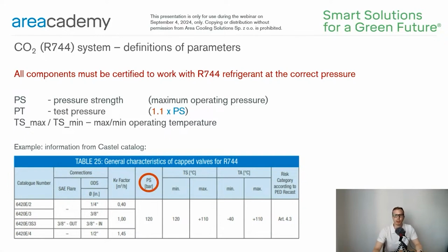When performing a CO2 installation, it is crucial to remember that all components of the system must be certified to work with CO2 refrigerant at the required pressure. Remember to always pay attention to the PS pressure strength values of each line and the corresponding safety valves. Do not use fittings, service valves, safety valves, or other components with insufficient PS value. Always check the specifications of the component you want to install, as you can see in the example table from Castel catalog. Here you can see the information about the PS for this component, 120 bar.